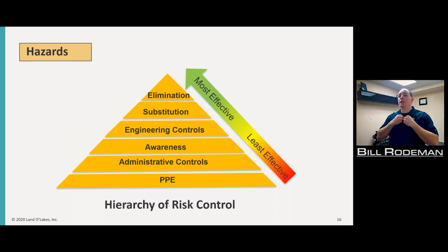You got to make sure that your shirt's actually buttoned all the way down, it's tucked into your belt, and when you're wearing your balaclava, that it's tucked into your collar and not sitting on the outside. That way, if you're hit with an arc flash, it doesn't travel directly up underneath your balaclava to your neck and face. So you have to wear it the right way, and you've got to inspect it to make sure it's not damaged. It's only as effective as the person using it.